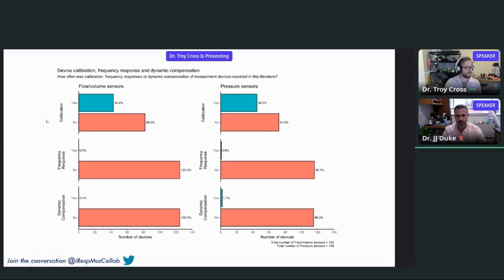We see in our studies, here on the x-axis, the number of devices. I didn't choose the number of studies as the denominator in these fractions because some studies did use two different devices, so there will be more devices in this literature than the number of studies. So we expressed it as a number of devices. Of all devices reported in this literature search, about 65% did not say anything about calibration. And 100% said nothing of the frequency response. And if that frequency response was poor, did they compensate for it?